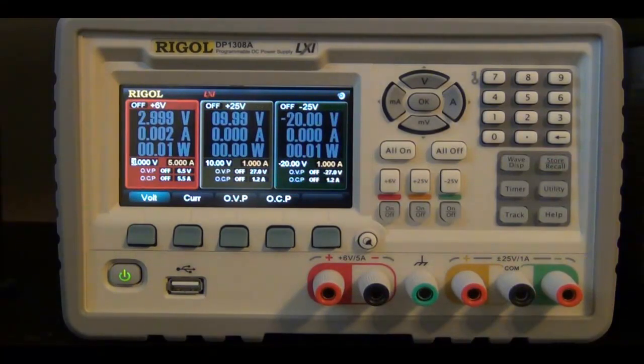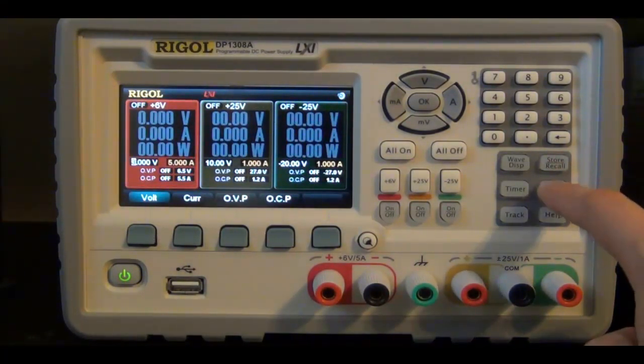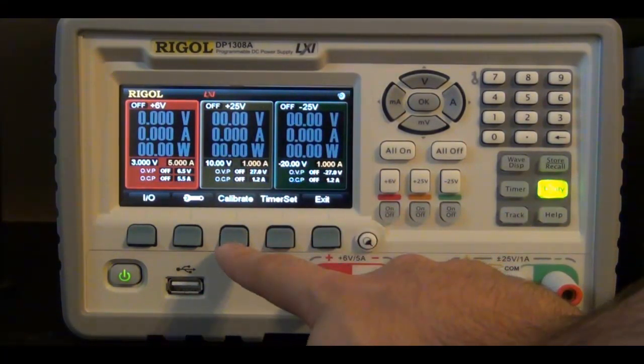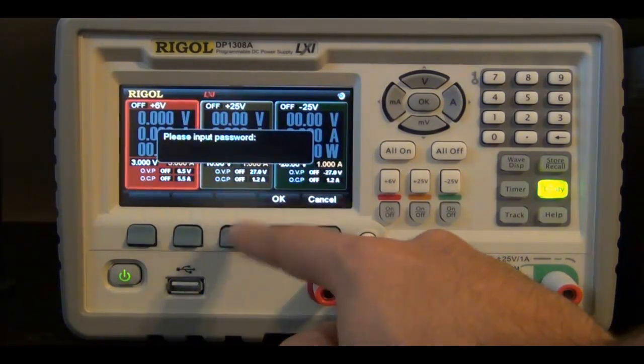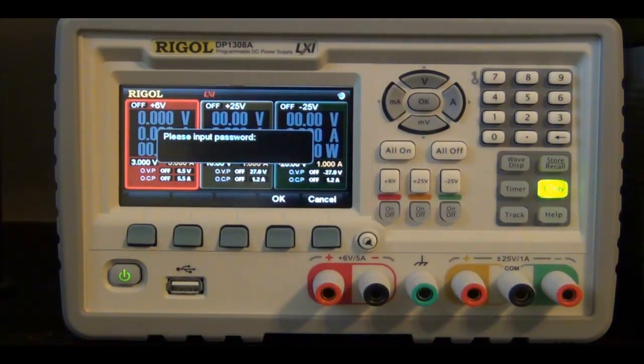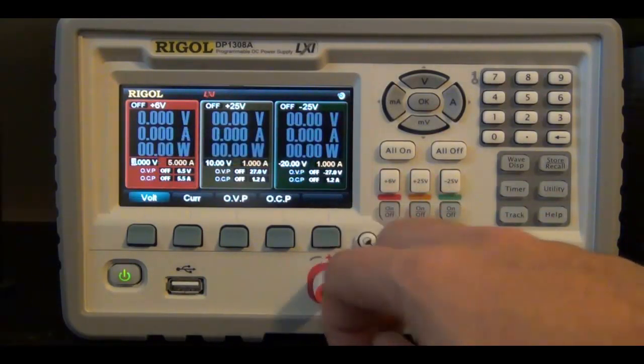So I was talking about the calibration. If you go under utility, there is a button called calibrate. If you press that, it asks you for a password. The calibration files are password protected, but if you contact Rigol, they will give you the password and they will help you calibrate this yourself, or of course you can send it back to the factory and they will do a full calibration. I'm not going to mess with the calibration right now, but it is important to know that that function is available for you. So I'm going to get rid of that.